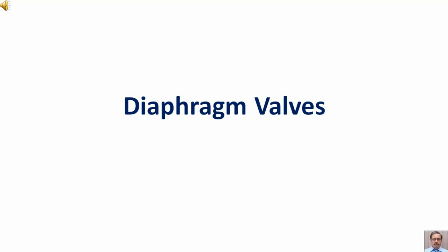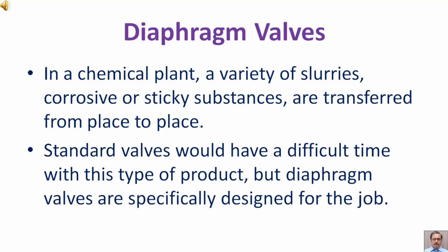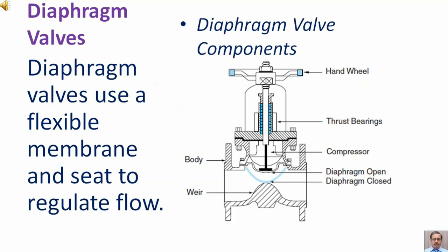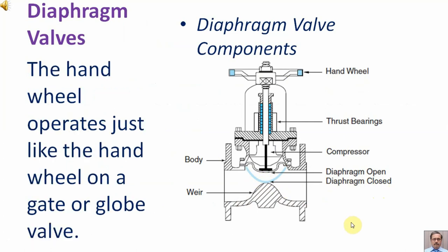In a chemical plant, a variety of slurries, corrosive, or sticky substances are transferred from place to place. Standard valves would have a difficult time with this type of product, but diaphragm valves are specifically designed for the job. Diaphragm valves use a flexible membrane and seat to regulate flow.